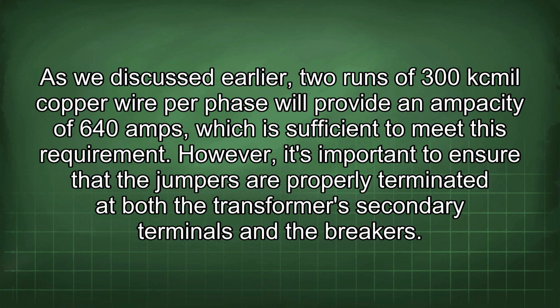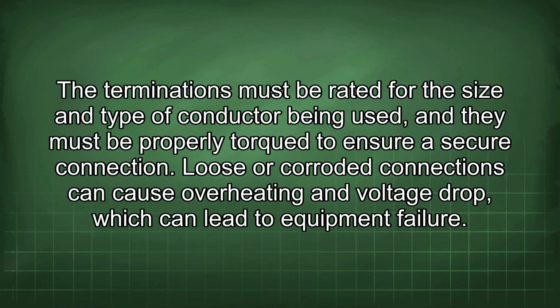However, it's important to ensure that the jumpers are properly terminated at both the transformer's secondary terminals and the breakers. The terminations must be rated for the size and type of conductor being used, and they must be properly torqued to ensure a secure connection. Loose or corroded connections can cause overheating and voltage drop, which can lead to equipment failure.